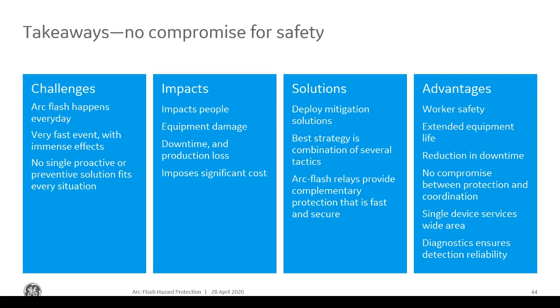extended equipment life. You're subjecting equipment to less arc flash energy, so less stress. A reduction in downtime: you will probably be able to reduce the damage caused by the arc flash and repair it in a timely manner. You're not compromising protection and coordination, for example with a low impedance differential relay, there's no coordination required. So you could still trip for faults on the bus and not trip for faults external to the bus. And diagnostics ensure detection reliability. Depending on the technique, like relays and communication, you're constantly doing diagnostics of the system, and you can tell when something's wrong so that you can go out there and maintain it.